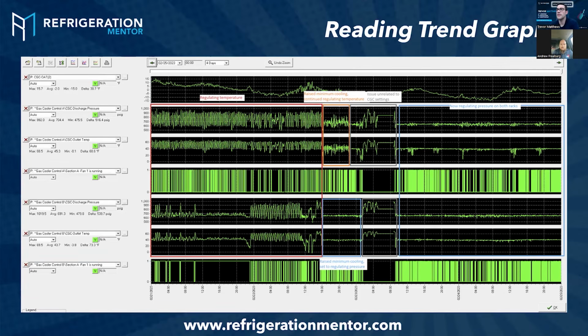You can see how it's kind of hunting, going from 900 psi in the gas cooler discharge down to 600, up to 1,000, down to 700. It's been doing that for days and weeks. The system's still running and maintaining temperature, but it's not running efficiently, and you start running into issues. You can see the technicians went in there and fine-tuned it, changed a few set points to test it out, and now you can see how they're running like a straight line, at 700 psi. This is something you can learn to read from trend graphs, and these are the things you need to take the time on.